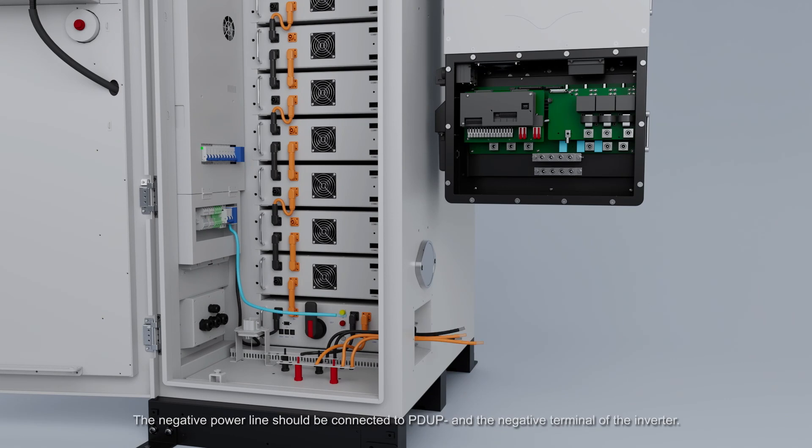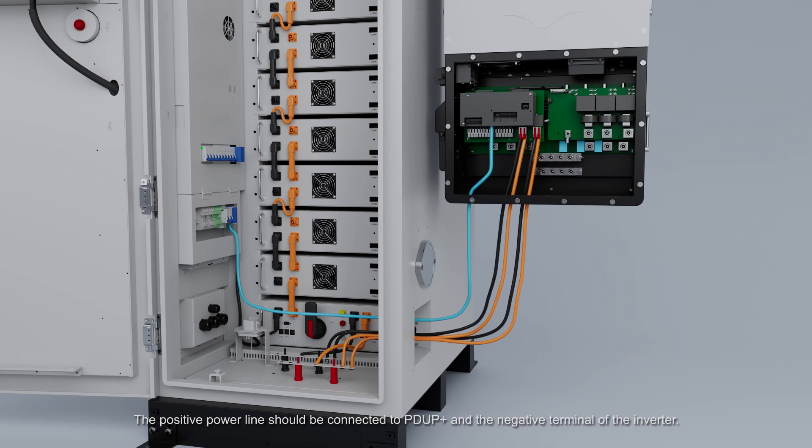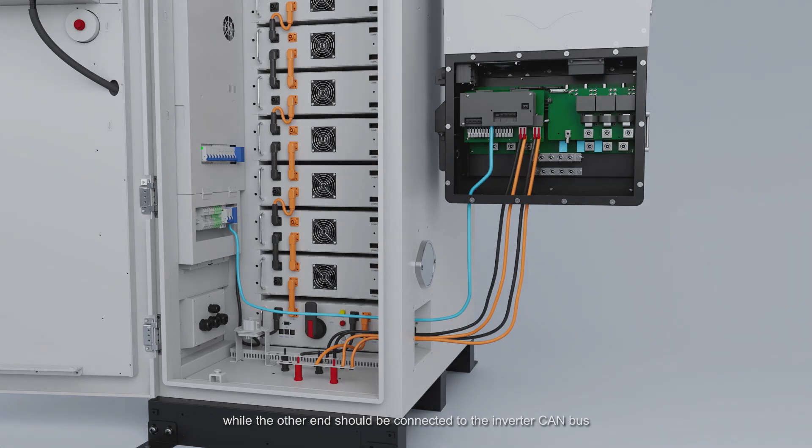When connecting the device to the inverter, the negative power line should be connected to PDUP- and the negative terminal of the inverter. The positive power line should be connected to PDUP+ and the positive terminal of the inverter. One end of the communication cable should be connected to the lightning protection communication device through the cabinet, while the other end should be connected to the inverter CAN bus.